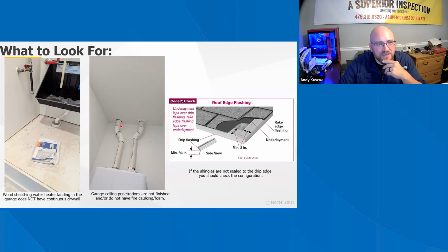And then this is kind of the same thing. This is the upper portion of that water heater where they did not seal the ceiling penetrations, which is voided, which has compromised the fire rating of the ceiling going into the attic. And then here is the Code Check diagram. So I love Code Check. I use it a lot.